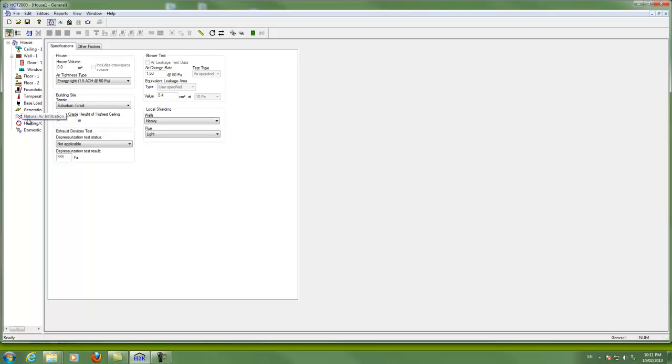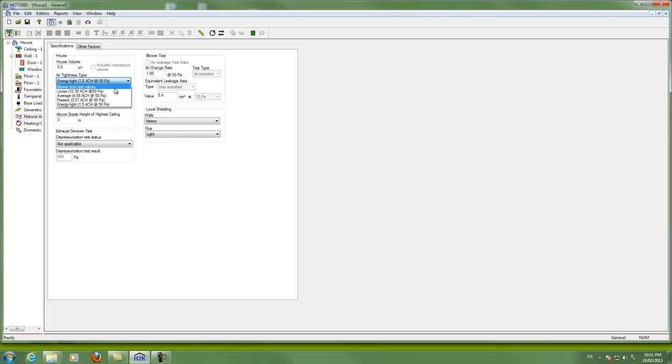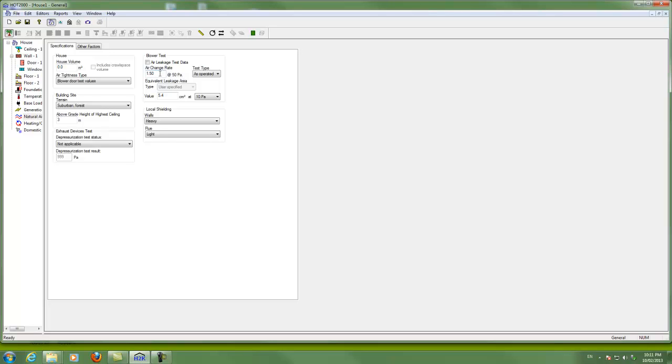Natural air infiltration, this is where we select how leaky the house is. And hopefully you have blower door data, in which case you can choose blower door test values. And this now changes to ACH at 50, the air change rate at 50, standard blower door software output. And we can also show the ELA here as well.